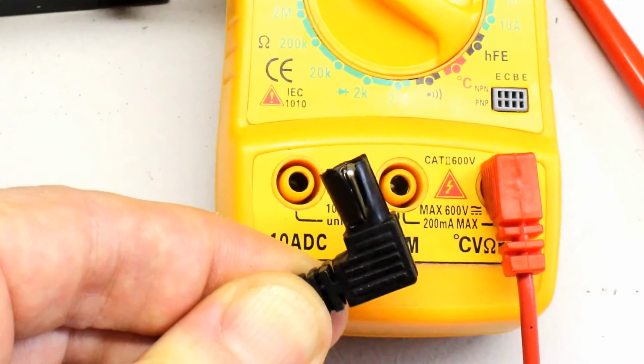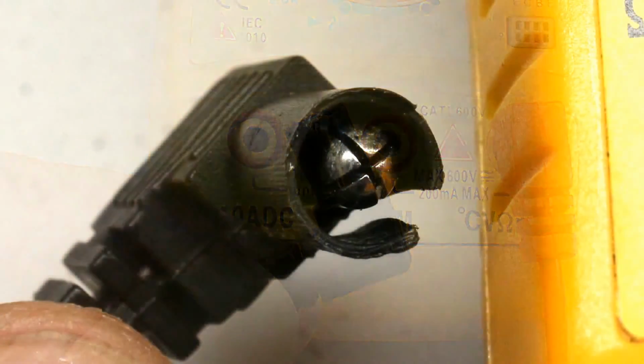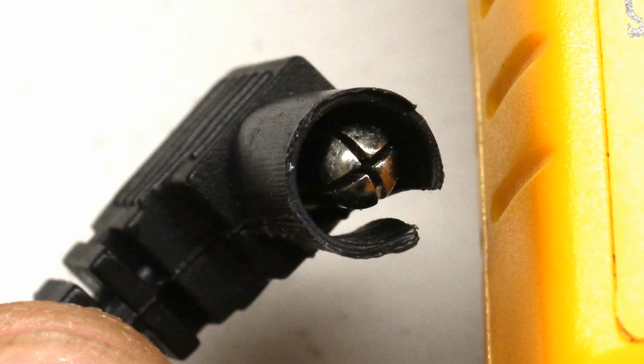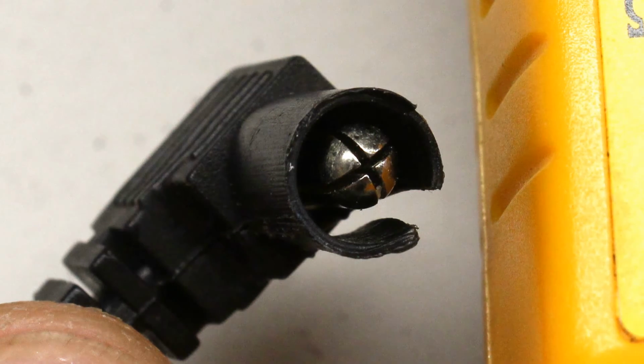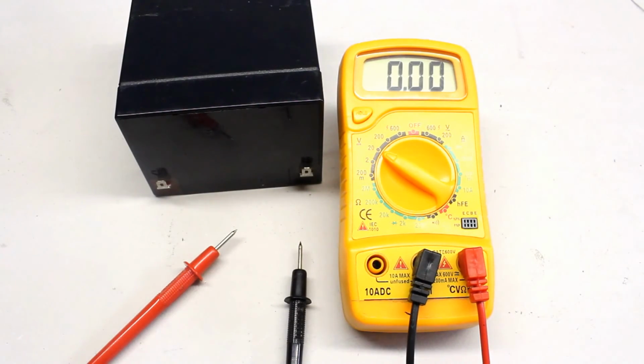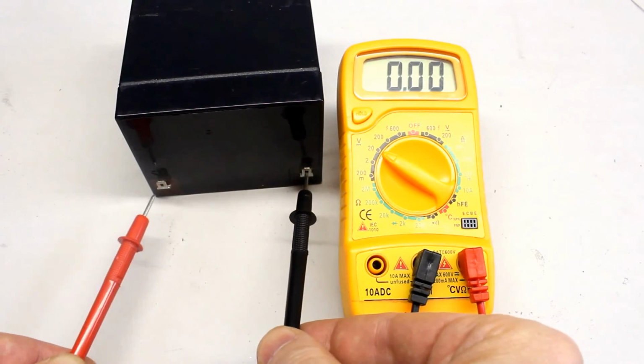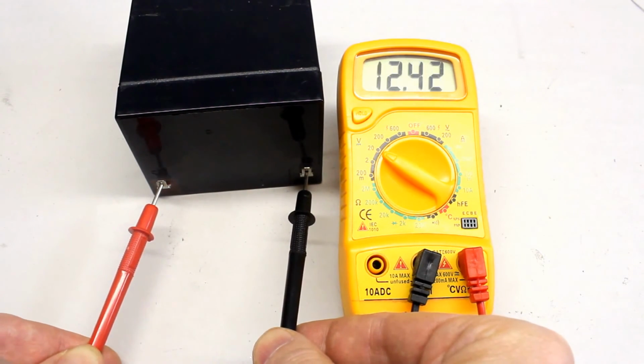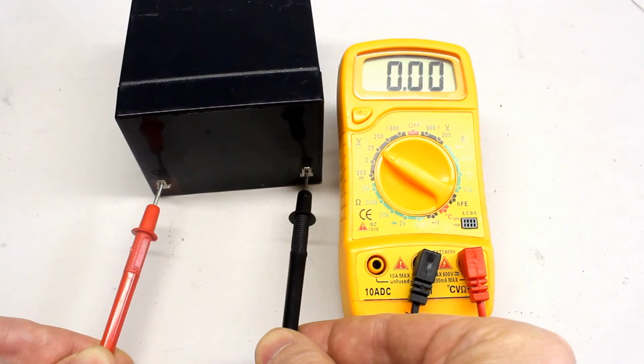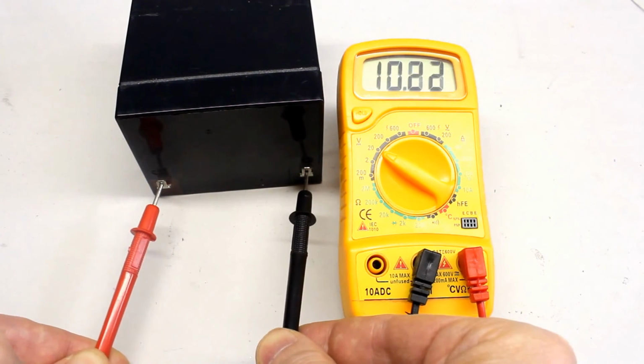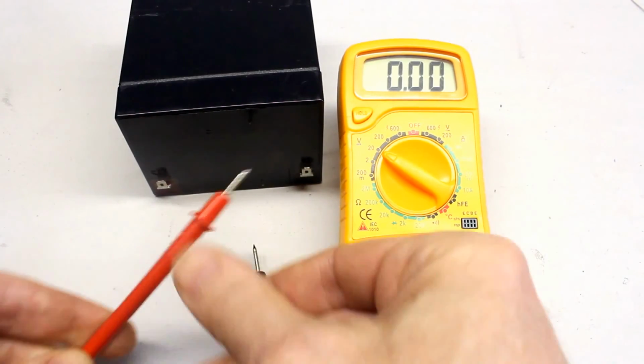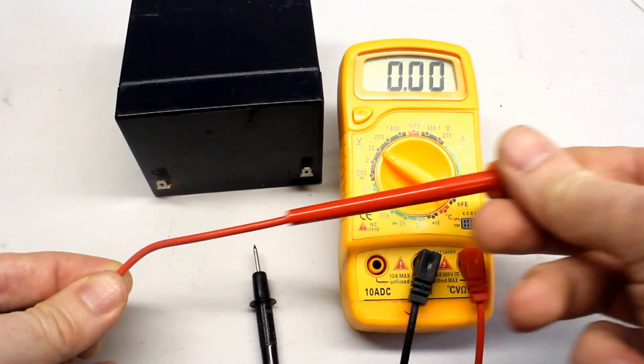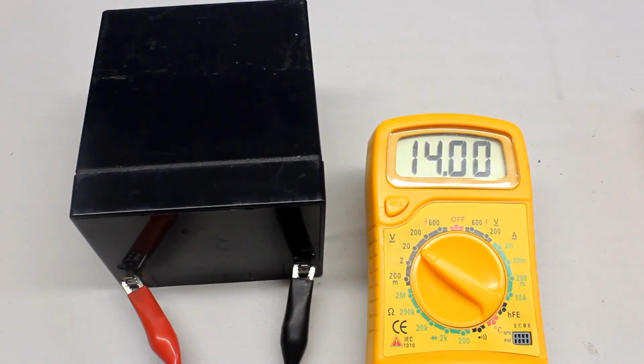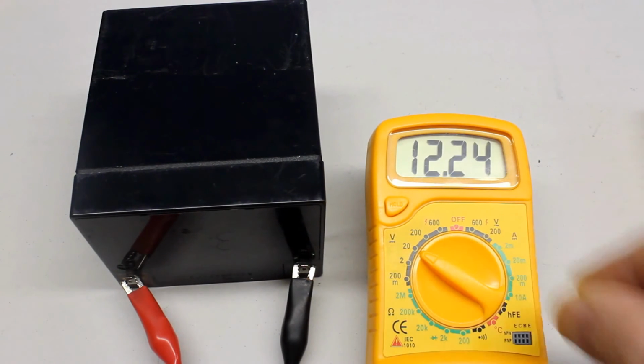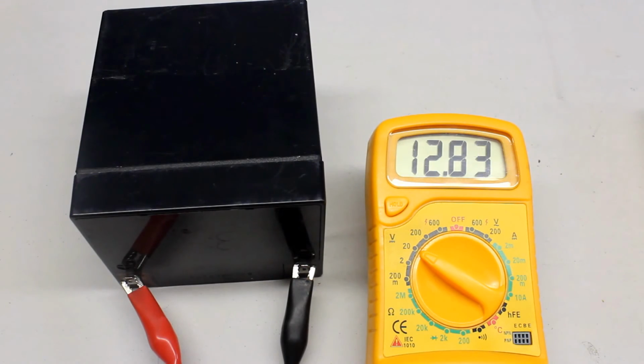Furthermore, the insulation of the test leads cracked during usage. Both defects concern the insulation of the multimeter, and there is danger to life while measuring high voltages. The cables are very brittle, which is why one of them cracked inside of the test probe, resulting in odd readings of the multimeter. This can become very dangerous if you rely on the reading of your multimeter, assuming that an unknown circuit is not attached to a voltage source, but you simply couldn't detect it. The rotary switch of one device doesn't always snap in place correctly, causing wrong readings.